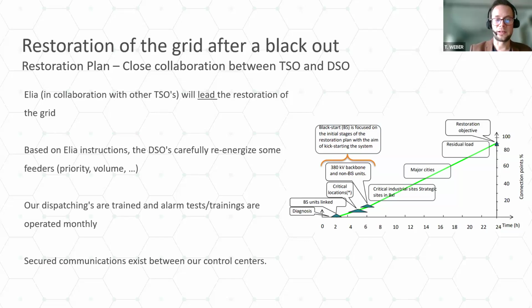But Harold said it very well. We have to focus on not destabilizing the grid. So we cannot just refeed all the substations at one time, it's too much, and it's a risk. So we need to make a selection of some feeders based on the consumption, based on the priority, and so on. So it's really something very important.